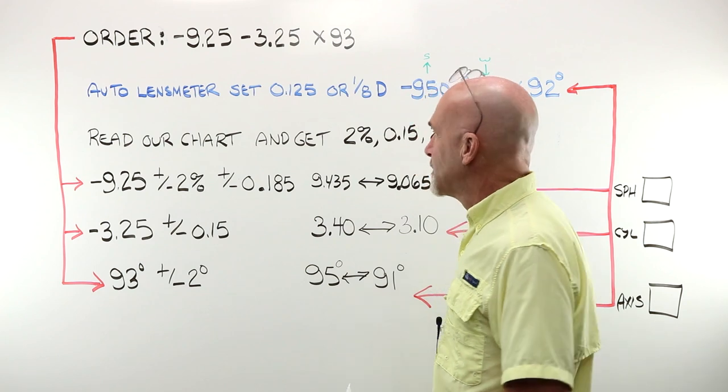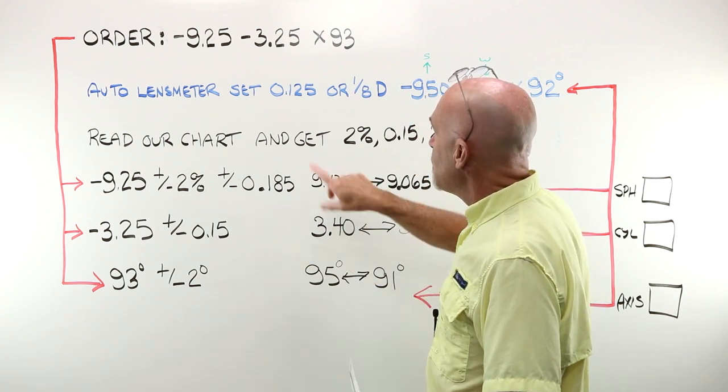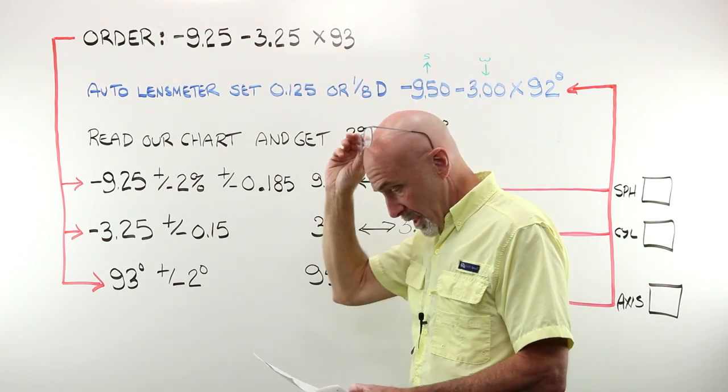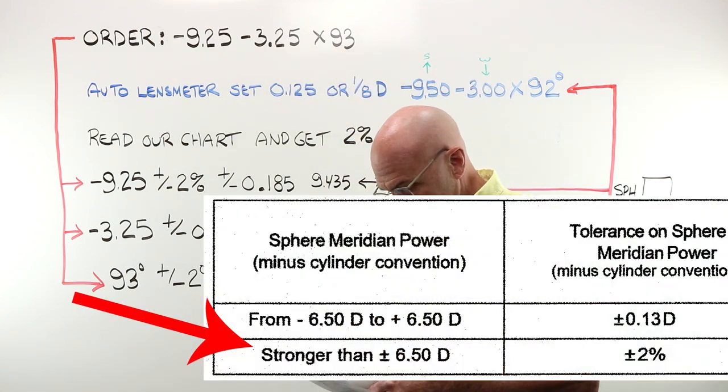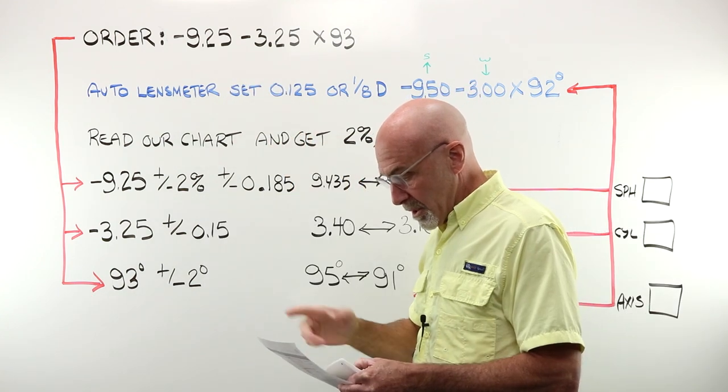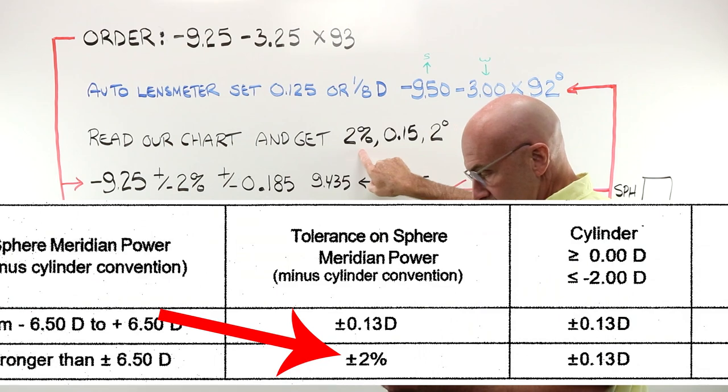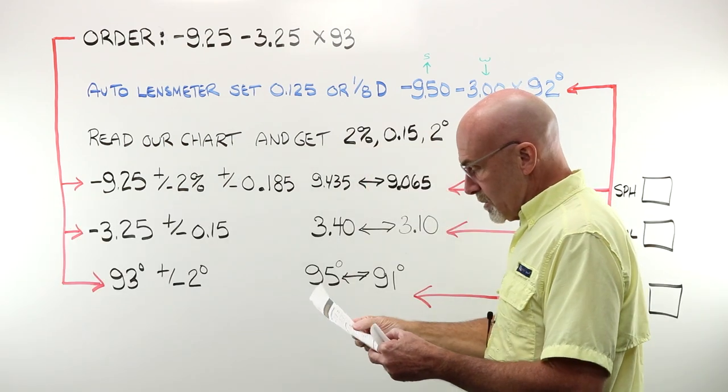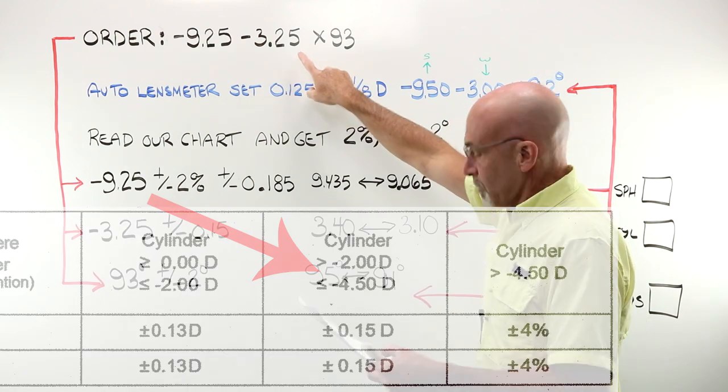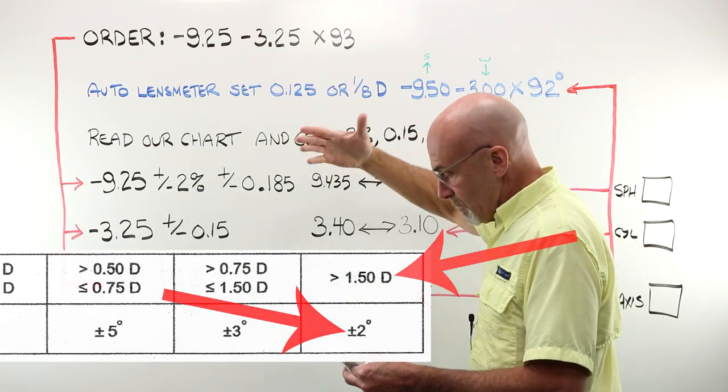Let's figure out what tolerance is for 925, 325, and 93. Well, let's see. Sphere meridian power stronger than 650 certainly tells us we have plus or minus two percent. Our cylinder falls between minus two and minus 450, so that gives us 0.15 plus or minus. And obviously our cylinder value is well over 150, so we have two degrees there.